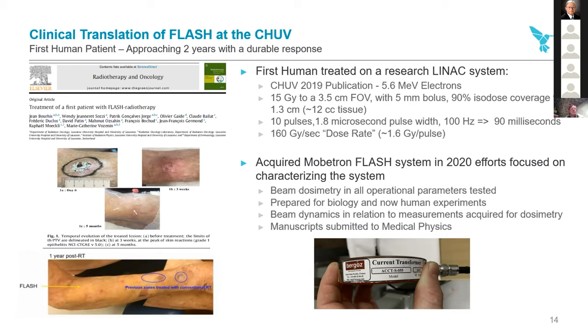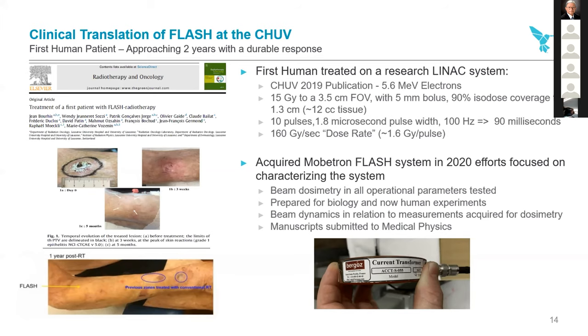They acquired the Mobetron last year and spent a lot of effort in a difficult year characterizing the system's dosimetry. All operational parameters have been tested, and they have prepared for biology and human experiments. They even performed their own independent current transformer measurements to independently monitor the beam current in various modes and correlate to the dosimetry they've taken. Those results have been turned into two manuscripts in medical physics, and this community will get to see those measurements published very soon, hopefully in 2021.